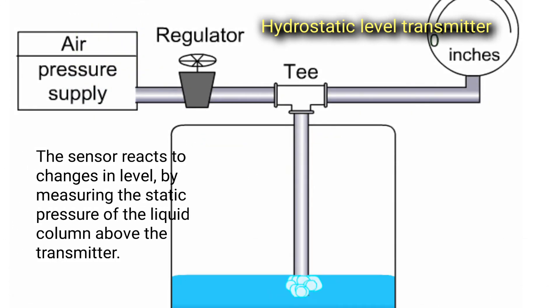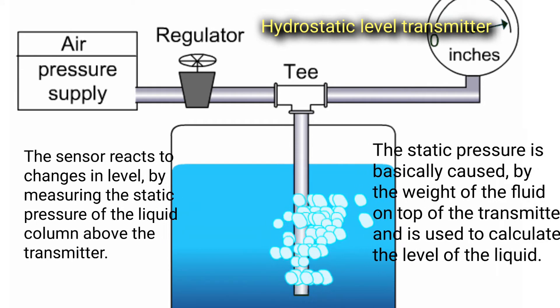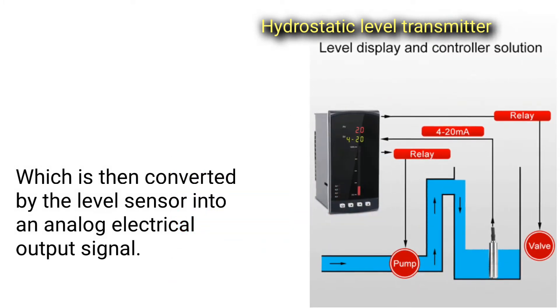The sensor reacts to changes in level by measuring the static pressure of the liquid column above the transmitter. The static pressure is basically caused by the weight of the fluid on top of the transmitter and is used to calculate the level of the liquid, which is then converted by the level sensor into an analog electrical output signal.